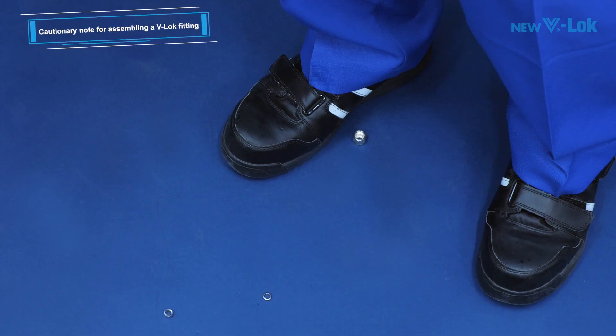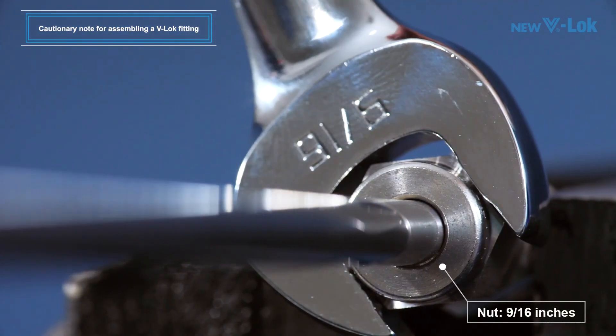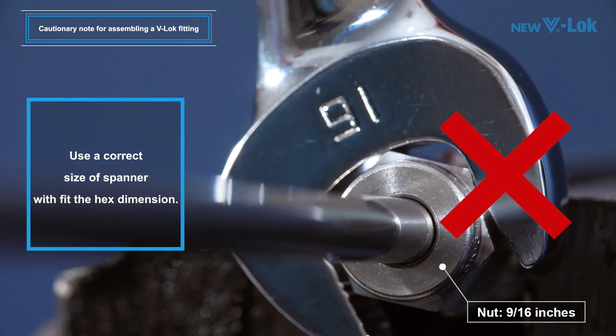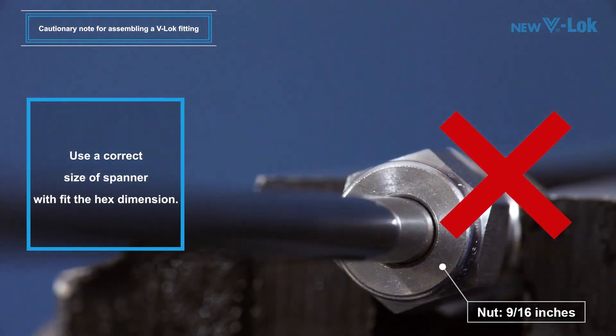Cautionary notes for assembling a V-Lok fitting: When a fitting was dropped by mistake, check for damage and attached foreign matter before use. Use a correct size of spanner that fits with the hex dimension. Please note that a millimeter base part and an inch base part require different tools when assembling a fitting.